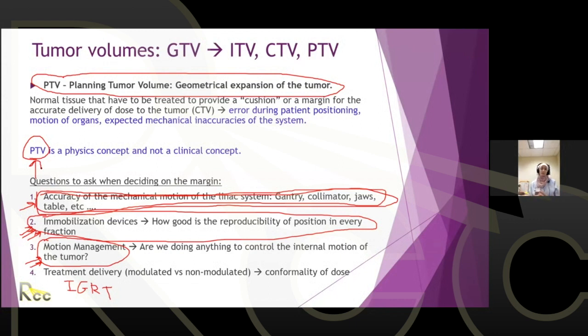So as a physicist, you have to be smart about it. If your machine is very old, and you cannot guarantee tolerance to 2 millimeters or less, then you have to tell the radiation oncologist, the chairman of the department, what you can treat on this machine. I will not treat head and neck on this machine if it cannot guarantee 2 millimeter or less accuracy. I will refuse to treat it.